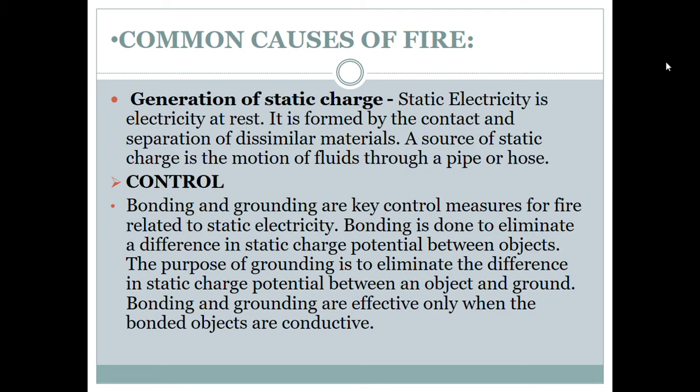Static electricity: static electricity is electricity at rest, formed by the contact and separation of dissimilar materials. A source of static charge is the motion of fluids through a pipe or hose. Bonding or grounding are key control measures for fire related to static electricity. Bonding eliminates a difference in static charge potential between objects, while grounding eliminates the difference between an object and ground. Bonding and grounding are effective only when the bonded objects are conductive.